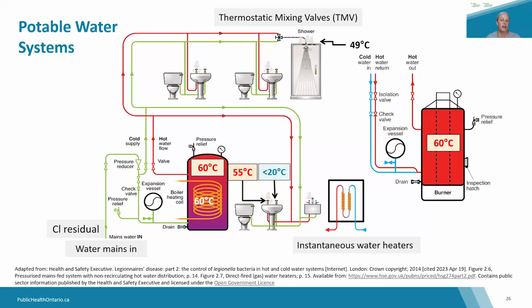However, because of this blending of water, it provides ideal temperature and conditions for Legionella growth at the point where the water is blended. So it's important to install thermal mixing valves as close to the point of use as possible to minimize the time and distance the water has to travel and remain at these warm, higher risk temperatures that would allow for Legionella growth. Next slide, please.